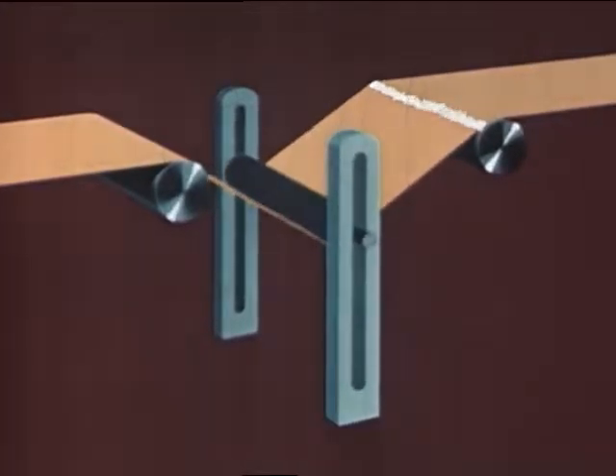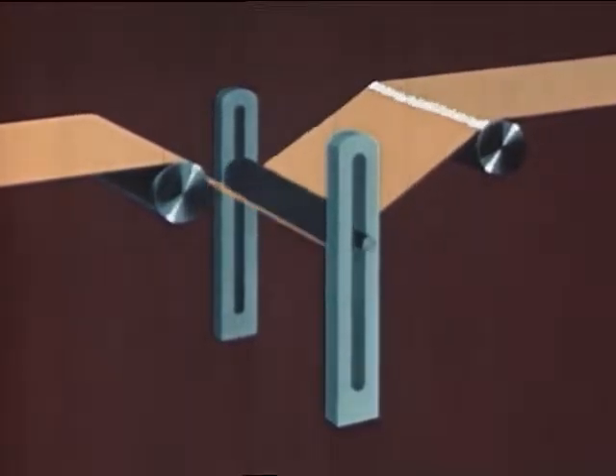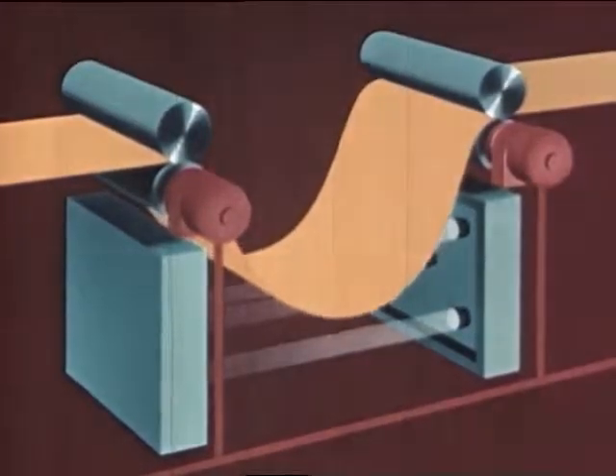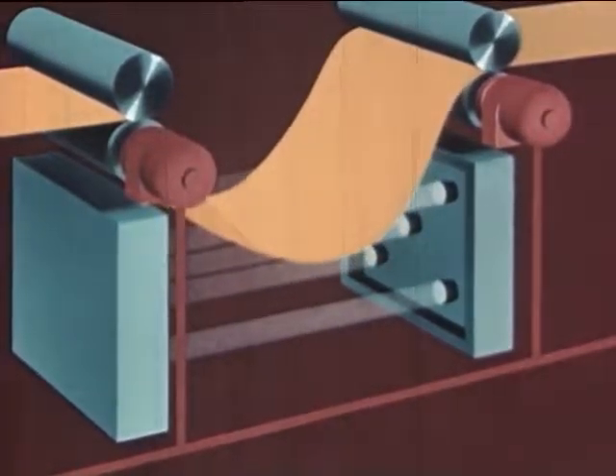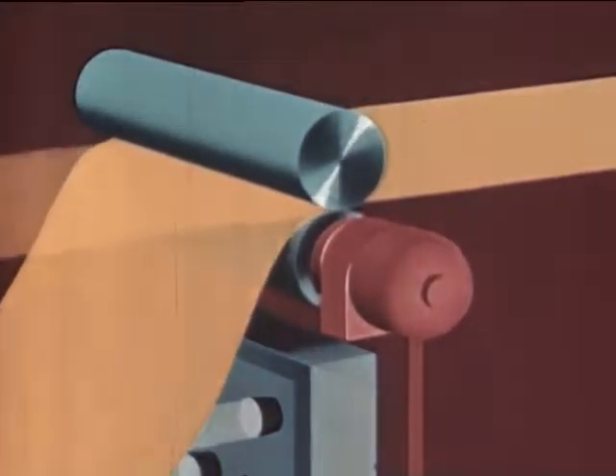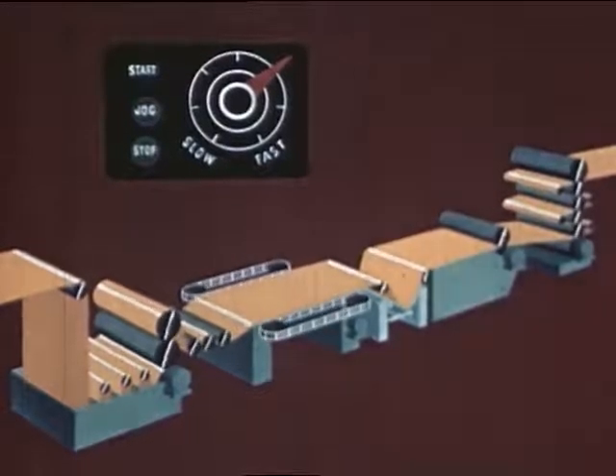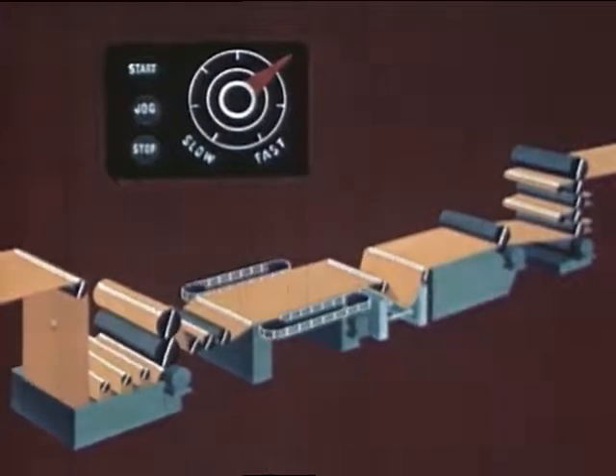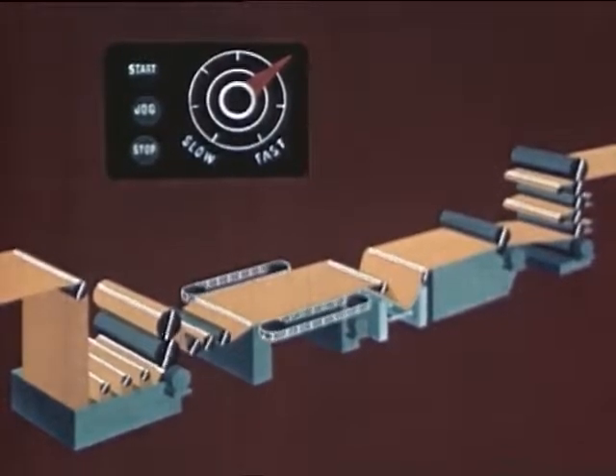A compensating gate is one of the most commonly used control devices for the coordination of range speed and fabric tension. Another type of automatic control uses the photoelectric eye to scan a loop in the fabric. Or so-called slip motors can be used, where the warp of the fabric is strong enough itself to act as a control belt, and thus slow down or speed up the motors for correct tension. This is the principle of electrically coordinated adjustable speed range drive, continuous processing for bleaching, washing, dyeing and soaping, printing and plain finishing.